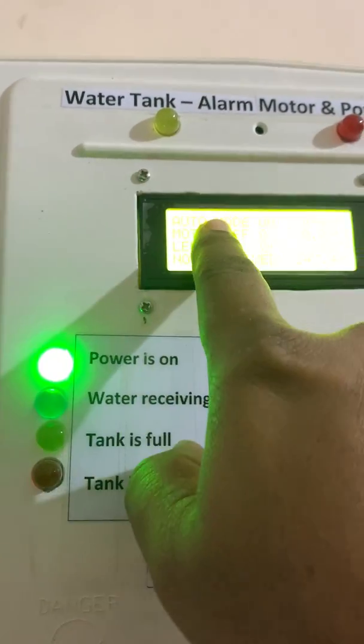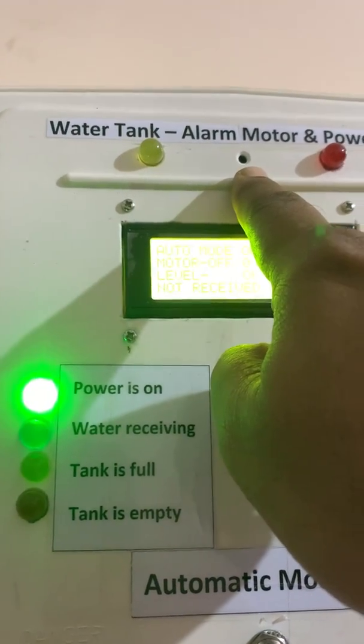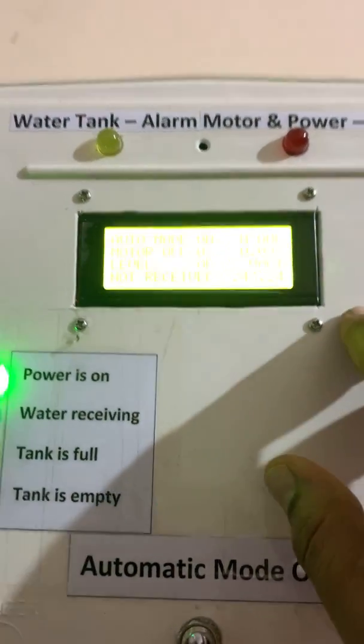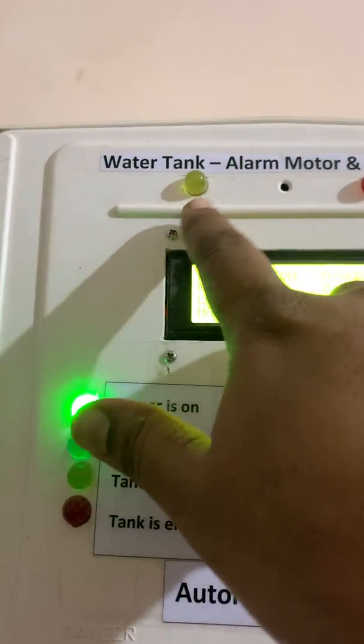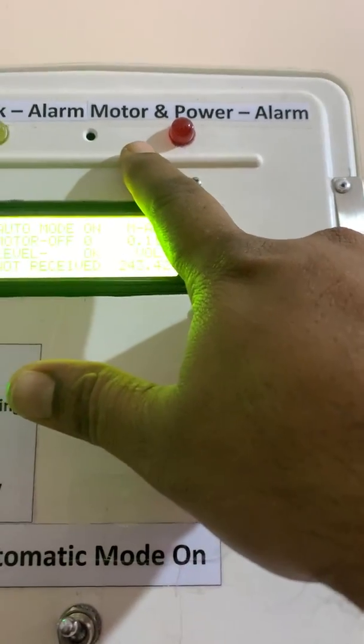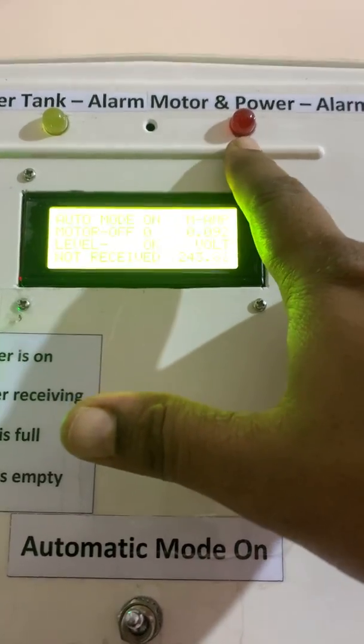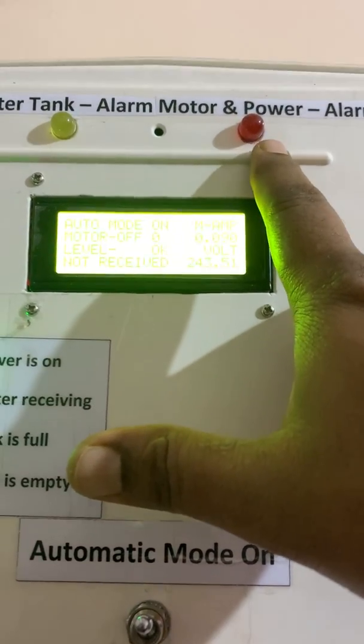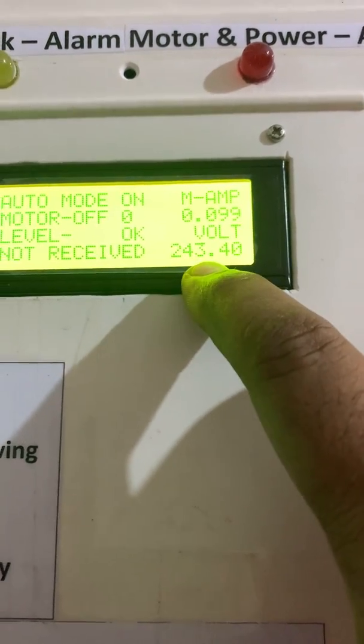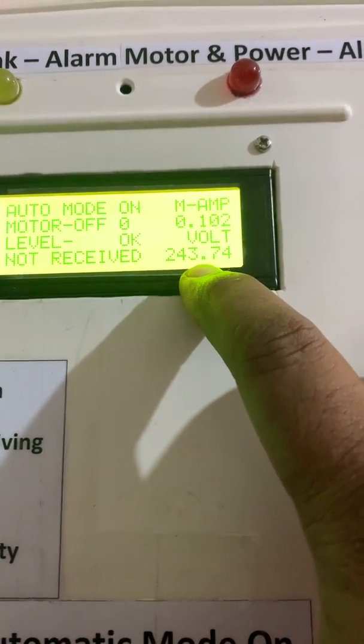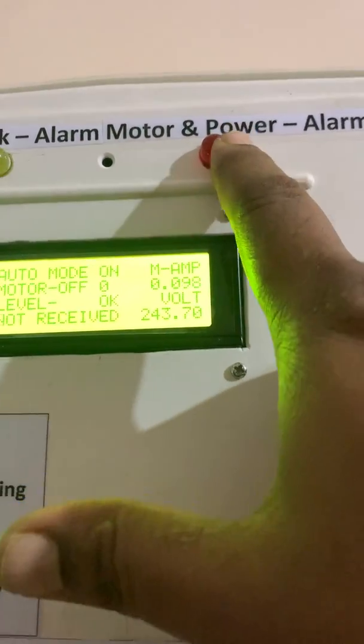Here also are alarm lights. One is related to the water tank. If there is no water receiving in the tank after running the motor, then this LED will blink and a buzzer will sound an alarm. The second LED is related to motor and power. If the motor is taking less current or higher current, or there's some voltage issue like higher voltage more than 250 or less voltage less than 180, it will alarm.